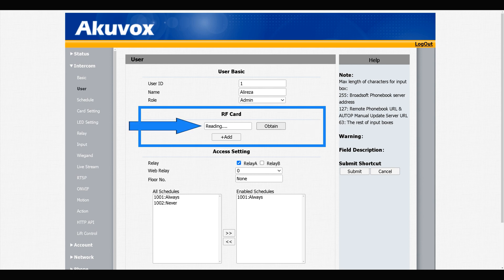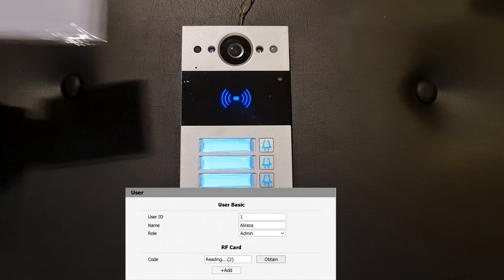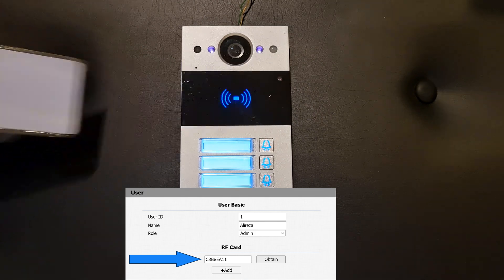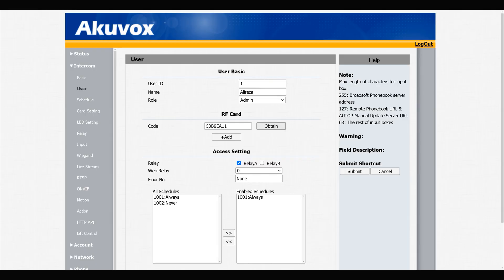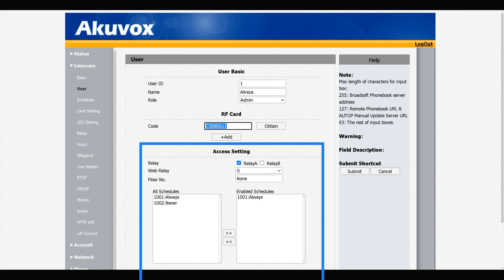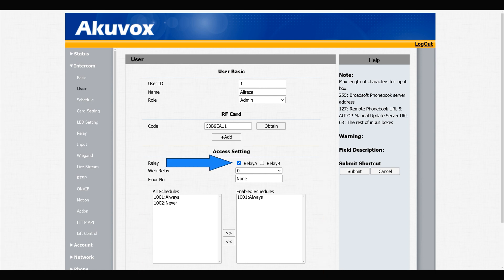Reader on the door phone starts reading. Swipe the card you want to add as an admin card. Door phone detected the card. In Access Setting, you can specify which relay out of two to be triggered when a card that's been added by admin card is read. By default, relay A is selected.